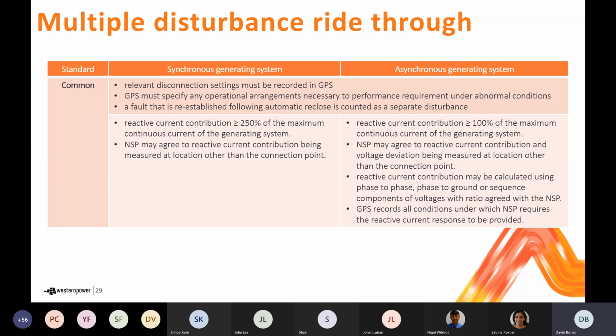And there's recognition again of the ability to vary where the reactive current contribution is measured through agreement with the NSP. And the reactive current contribution, there's recognition of different ways in which it may be calculated with reference to using either phase to phase, phase to ground, or sequence components of voltage. Again, provided that's been agreed with the NSP.